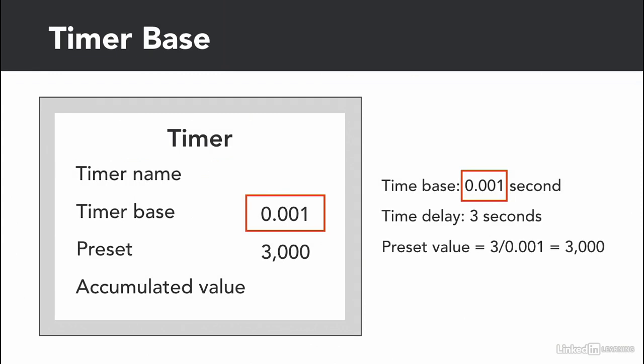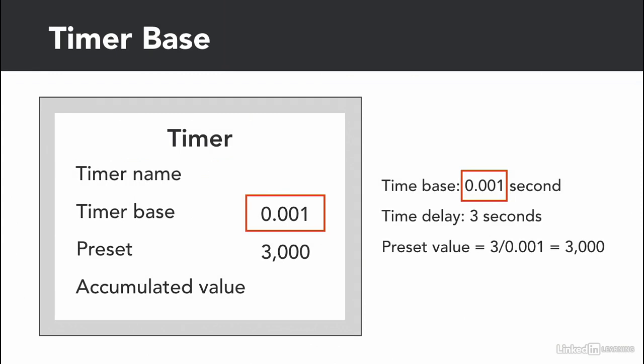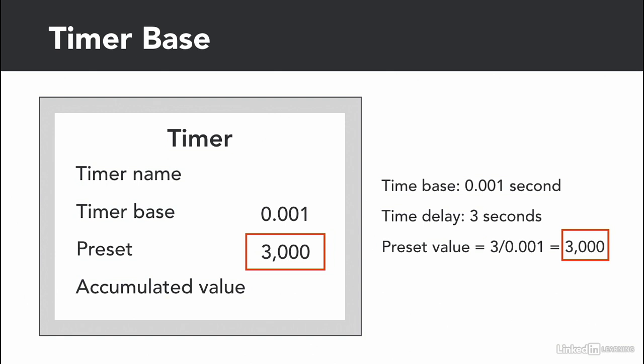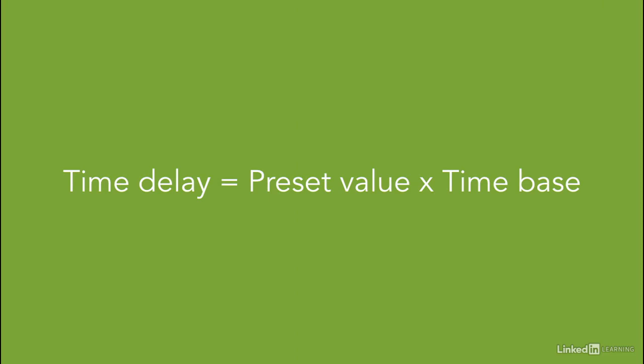So if the time base is 0.001 second, and you want to program a 3 second delay, then the number to put in the preset value is 3 divided by 0.001, and this equals to 3000. The equation is that the desired time delay equals the preset value times the time base.